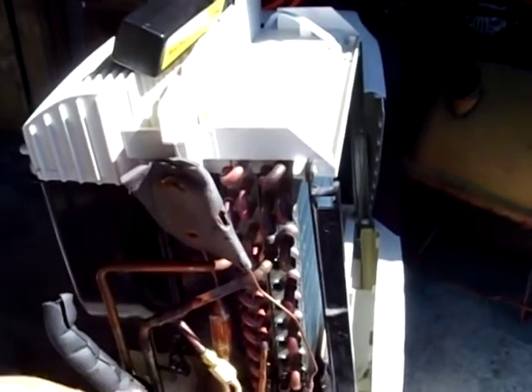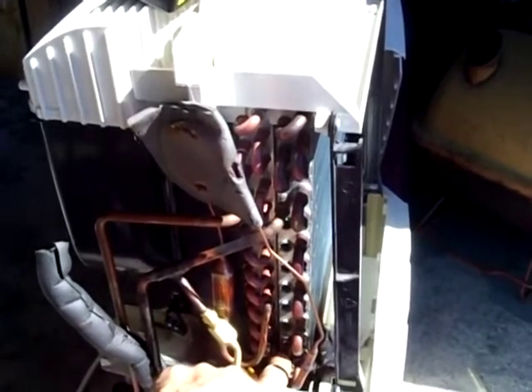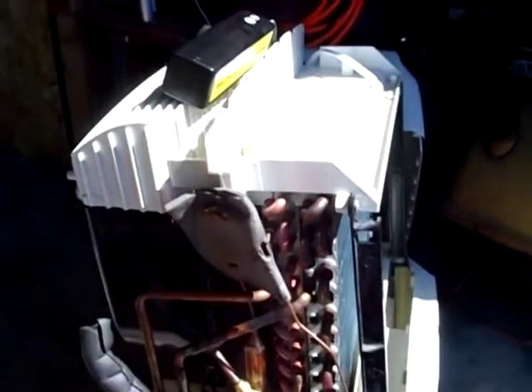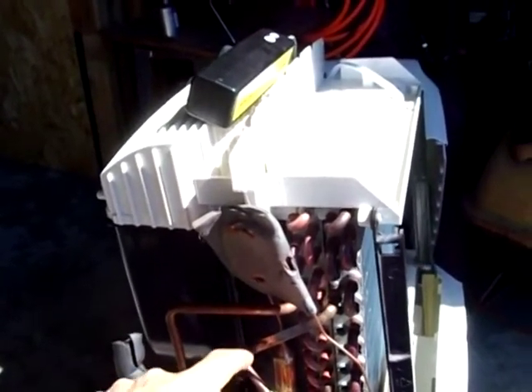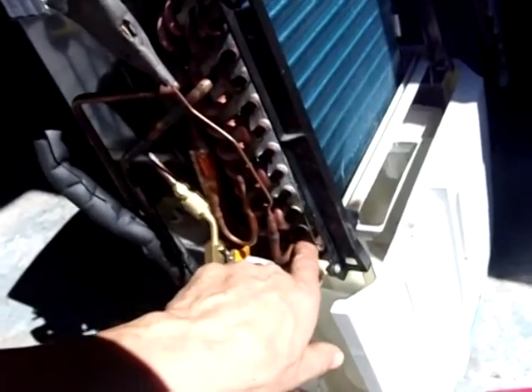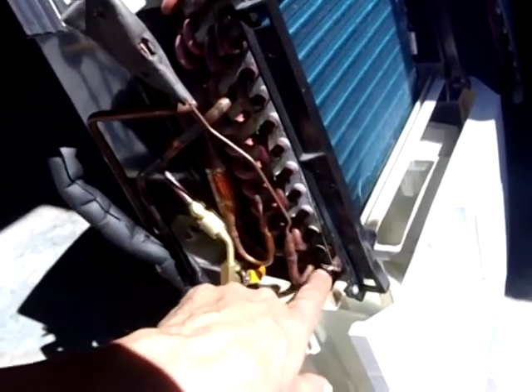Well, she's running. I put some refrigerant in it, and I checked it with the sniffer, and there were a couple false alarms, like if you put it near this tube that had refrigerant, it'll start triggering it there. But I ran it, I moved it around. It did trigger nicely by one of these fittings that was a little bit loose. Tightened it up, and then that went away. I checked my brazes here, never a problem here. This one, there were a few, like I said, false warnings, but then when I rechecked it, no problem. I put more refrigerant in it, and still no problem.